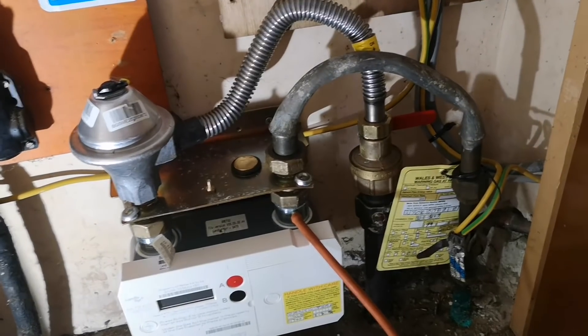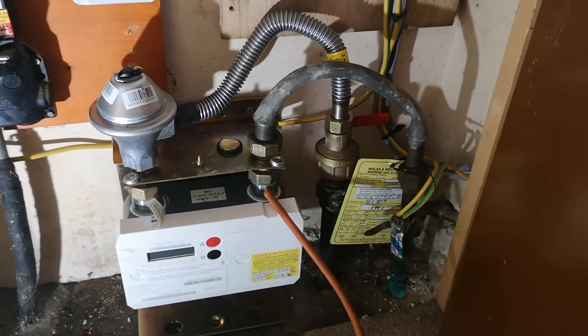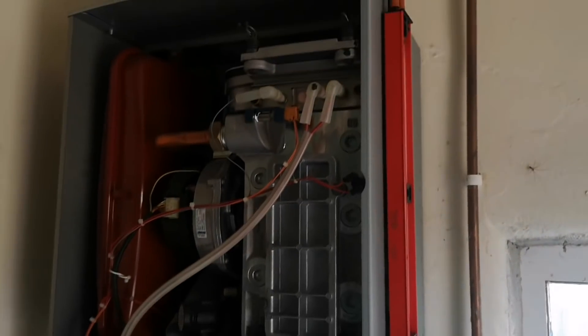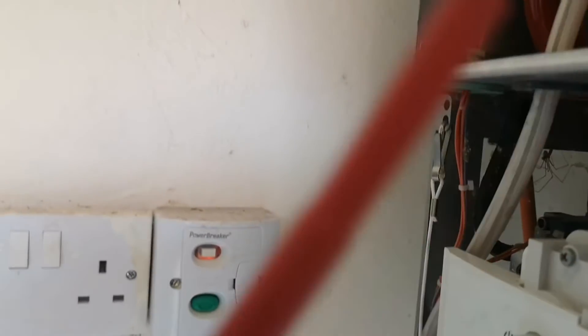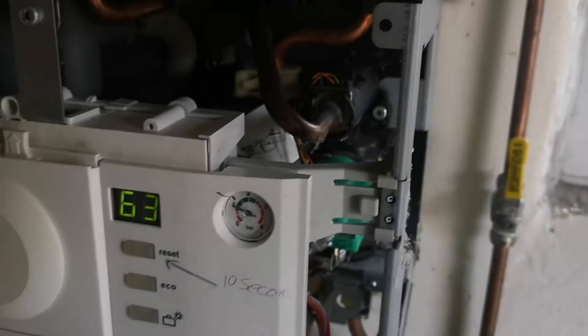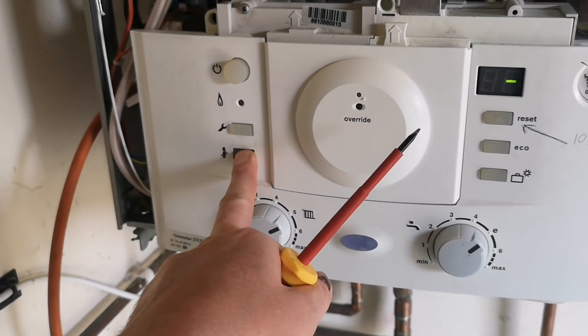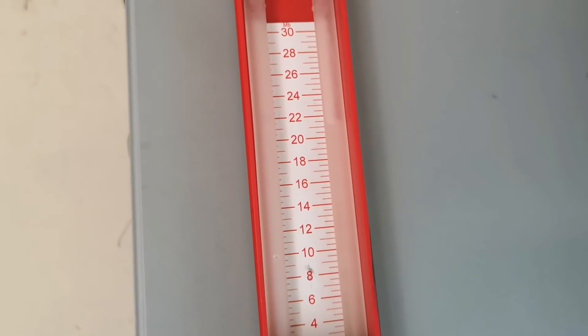We'll put a pressure test on at the boiler just to discount that - I'm going to have to change it anyway but we'll see what we're getting. Because we've got the kinked gas main, we've rigged up a pressure test from the gas valve and we're going to run the boiler on full rate just to see if we do have bad pressure. You never know - it could be okay. So we're putting the boiler into maximum mode.